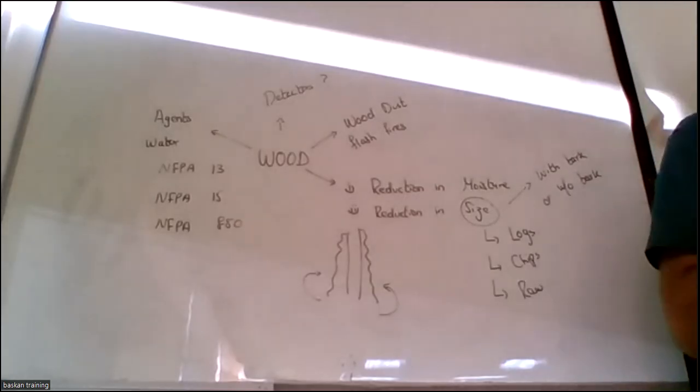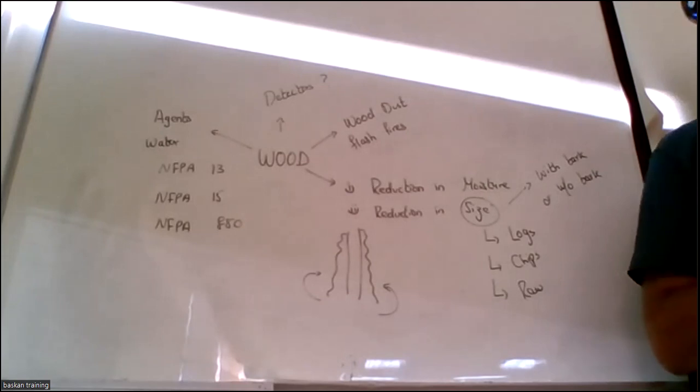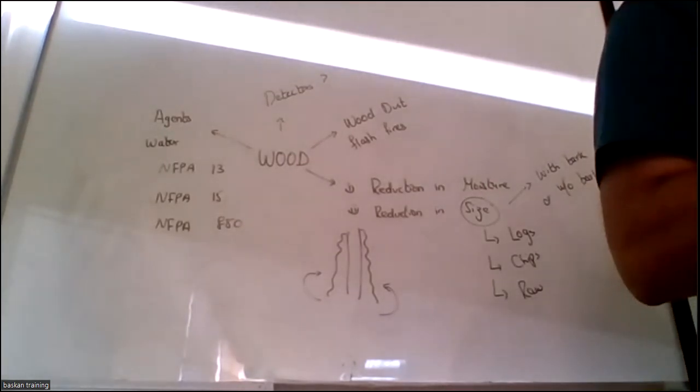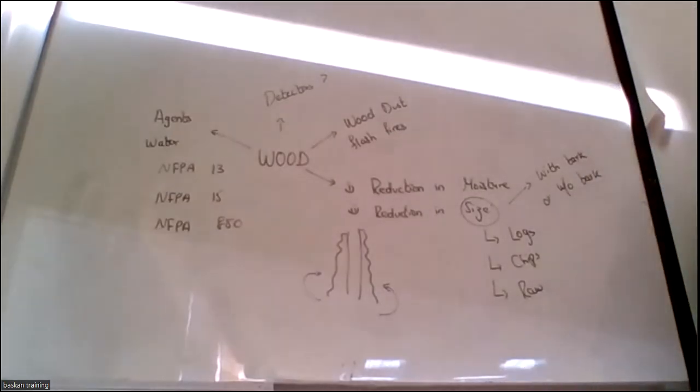Consultant approved, everything approved, the drawing is there, but the false alarm ratio was very high. They came for inspection, passed the drawing, everything passed, and it continued running. After 3 months, when we went to the facility to do the first maintenance, we found the panel was off. The owner had kept it off. He said, after every 2 minutes, I cannot bear it. Remove your device, my people are disturbed. We don't know what is going on, after every 2 minutes it's triggering the alarm.